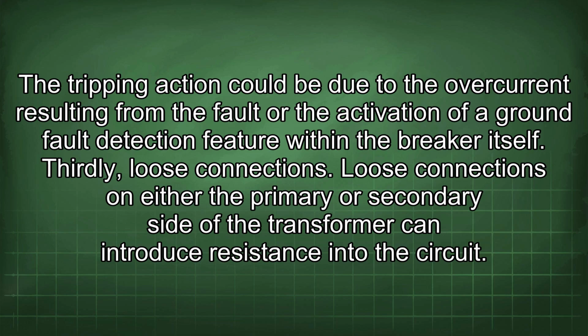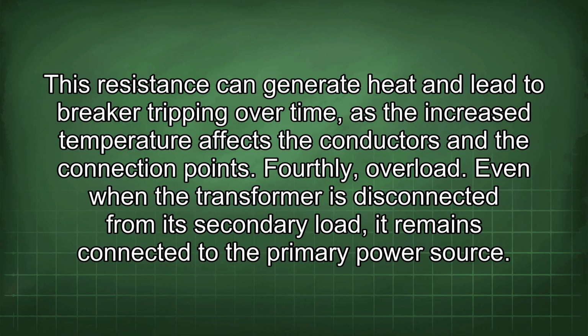Thirdly, loose connections. Loose connections on either the primary or secondary side of the transformer can introduce resistance into the circuit. This resistance can generate heat and lead to breaker tripping over time, as the increased temperature affects the conductors and the connection points. Fourthly, overload.